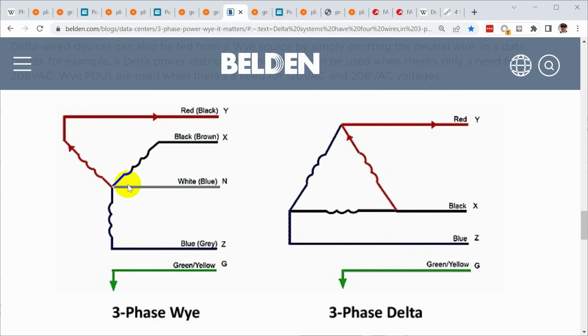And the reason for that is because we don't have to worry about making these individual legs 120 volts to the neutral, because there is no neutral. So you don't have to run a wire for the neutral. So you save money on copper, aluminum, bus bars, and all of the hardware associated with routing that. You don't have to pay for any of that. The downside, of course, is you don't have the neutral, so you don't have the ability to directly connect 120 volt loads. But if all you're running are three-phase loads, delta will work fine, and it's a less expensive option.